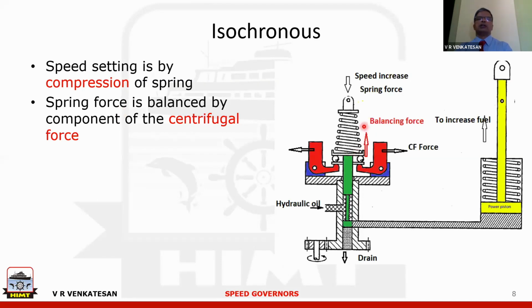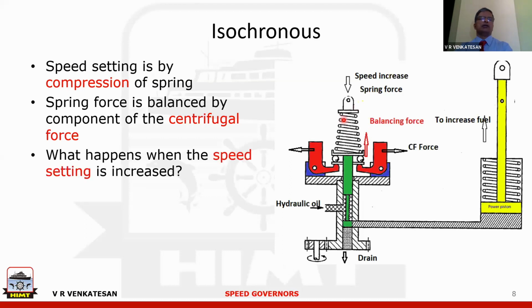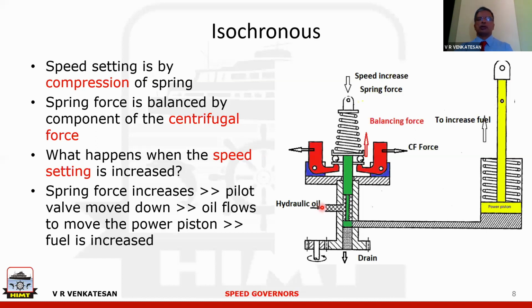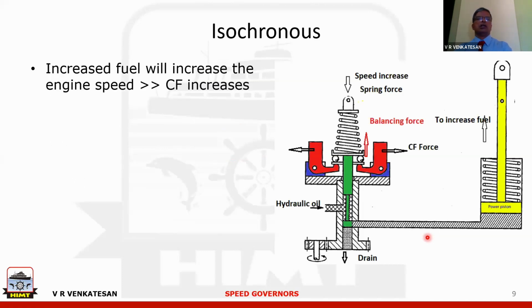That is this red colored force which we are seeing. The component of the centrifugal force acts this way through this mechanism called the bell crank. And when the speed setting is changed, what will be the result? For example, the spring force is increased. When the spring force is increased, what will happen is this pilot valve will be pushed down. As the pilot valve is pushed down, then the oil will flow from here into the power piston and the fuel will get increased. As the fuel is increased, the speed of the engine will increase again. And as the engine speed increases, centrifugal force will increase once more. And these two forces will be once again balanced. That means the spring force and the force of this will be balanced.